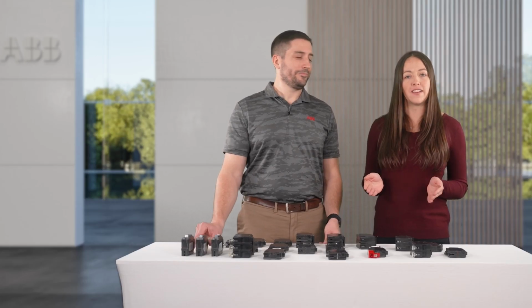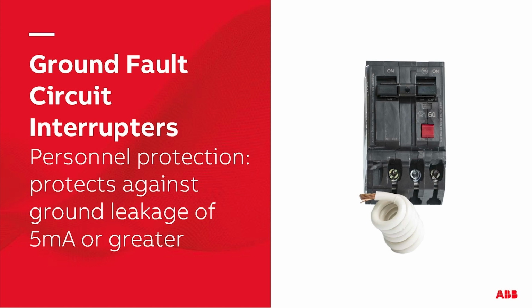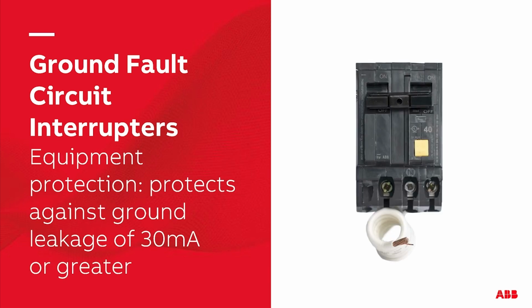There are two options available for ground fault protection. First is personnel protection, which protects against ground leakages of 5 milliamps or greater, and is mainly seen in residential and commercial applications. Second is equipment protection, which protects against ground leakages of 30 milliamps or greater, which is typically found in a variety of applications and industries, including de-icing systems, semiconductor manufacturing, heat trace systems, and many more.